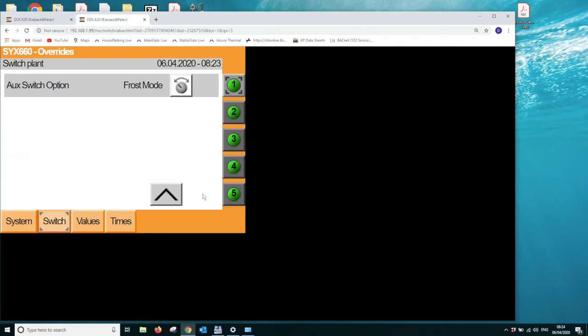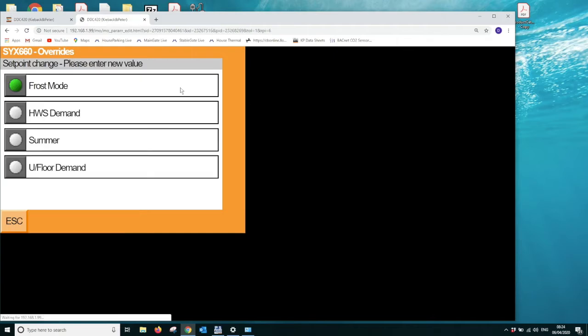The next option we choose is the auxiliary switch option, and as I just discussed, we want that to be used for hot water demand control. Frost mode is a holiday switch. The other option here is hot water demand, which is the one we're going to select.